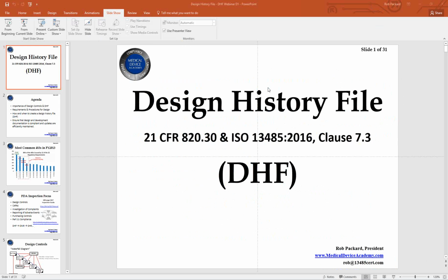That goes under design history. But they just want a summary of it. They don't want the whole thing and all the records like the DHF. So it's a summary. And all the contents of the DMR are included in the technical file because it's going to be the most current outputs. So that's important. If you have a design dossier, you're going to add to that revision history over time. And so oftentimes I will include that as cross-references to ECNs and ECOs.